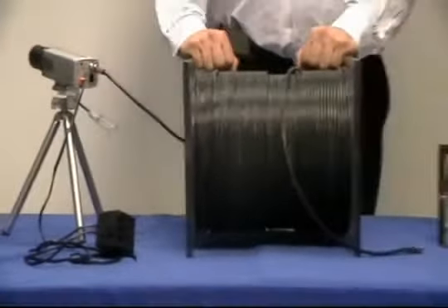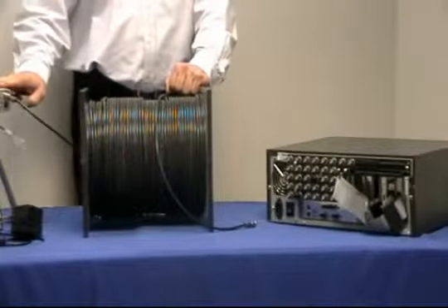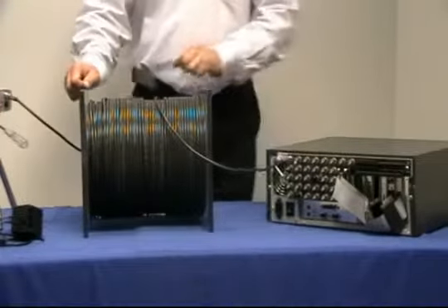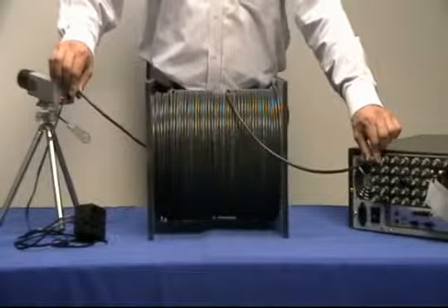In most traditional analog CCTV installations, the coaxial cable is routed in a home run fashion from the camera location all the way back to the DVR, which will be located in the security room or at the head end. Industry standards indicate RG59 coaxial cable has an optimum operating distance of approximately 750 to 1,000 feet. Field studies show the average length of installed home run coaxial cable being used in CCTV today is approximately 575 feet per camera. For our demonstration today, we're using 1,000 feet of RG59U coaxial cable.